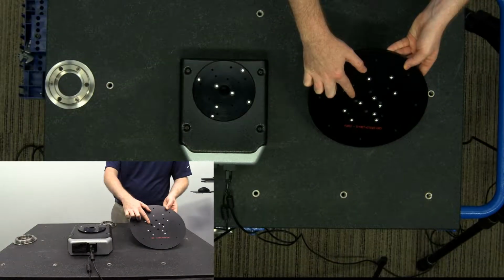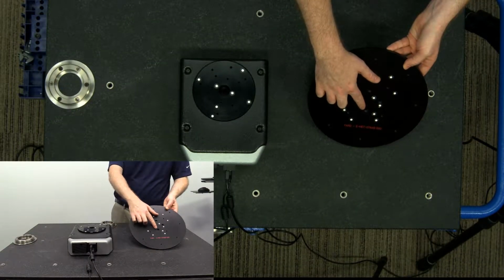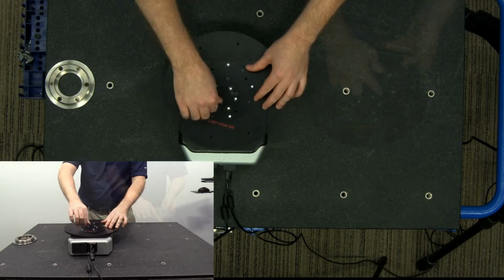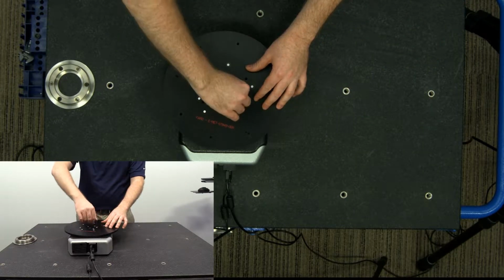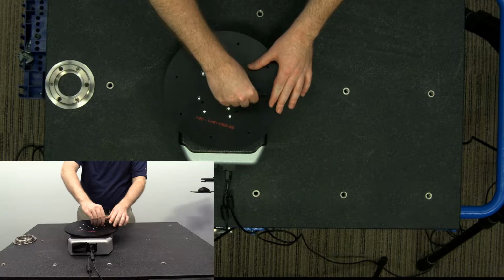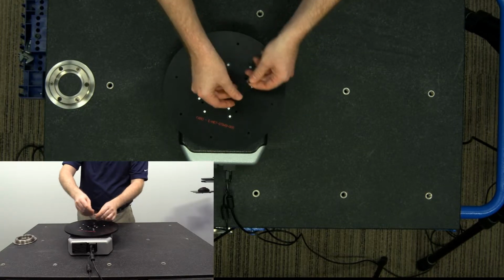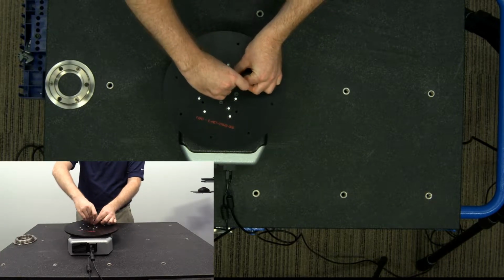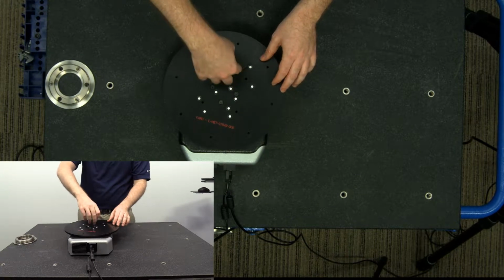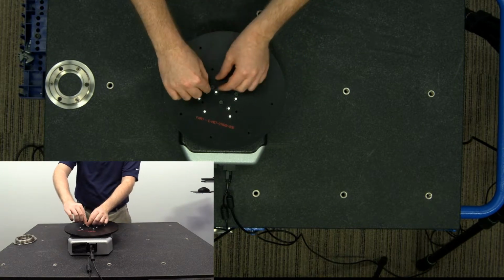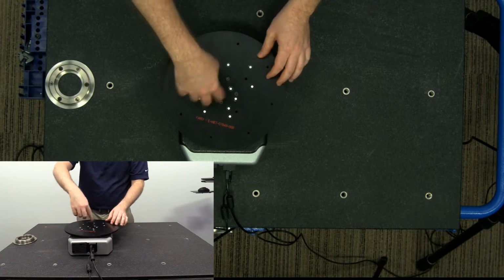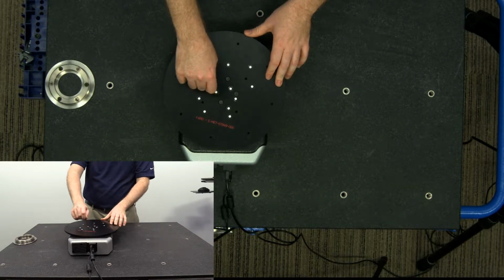Once the rotary table has stopped moving, attach the rotary table extension plate using the provided 4 screws and hex key. Ensure the targets are clean and in good condition. Replace any damaged targets and ensure there are between 7 and 12 targets on the plate. Now, we're ready to calibrate and align to the rotary table.